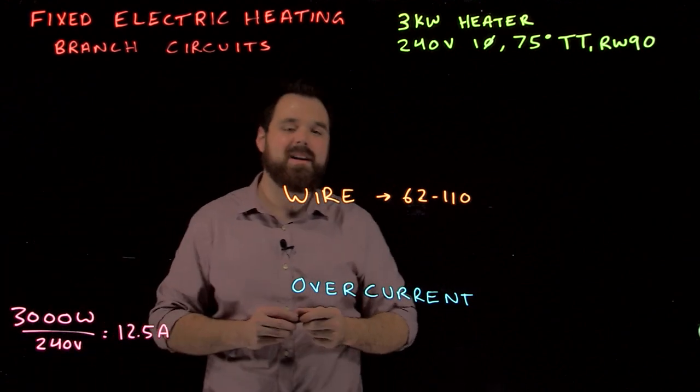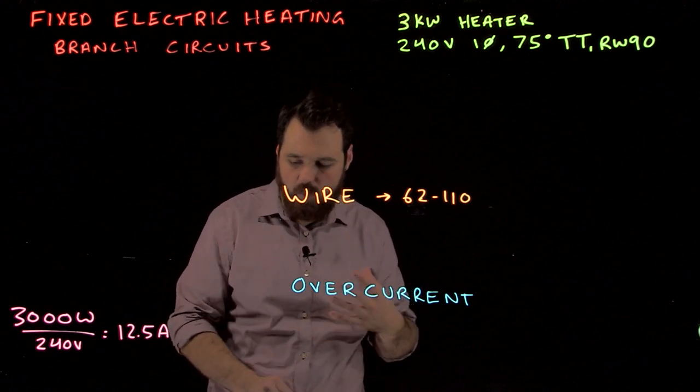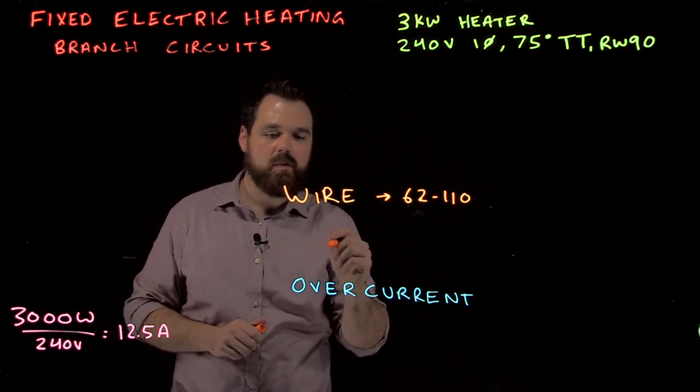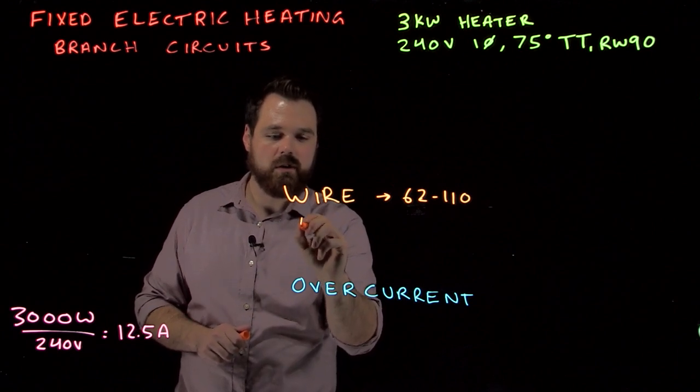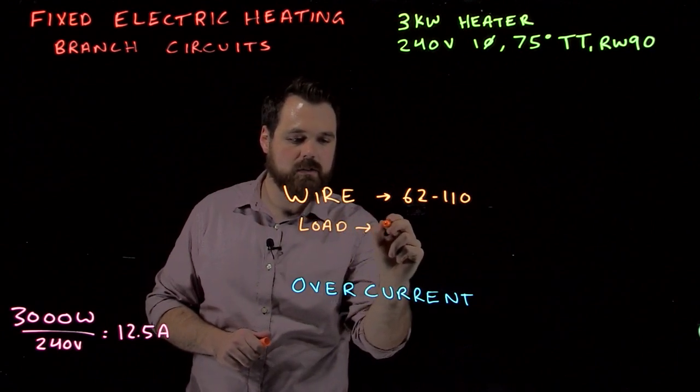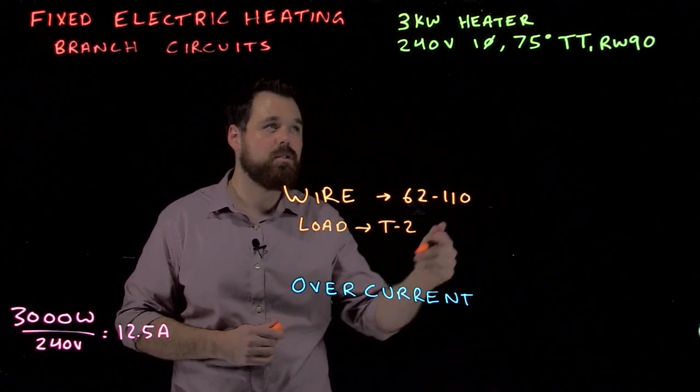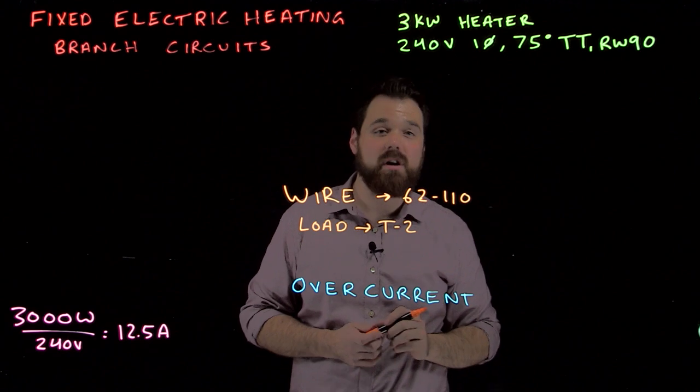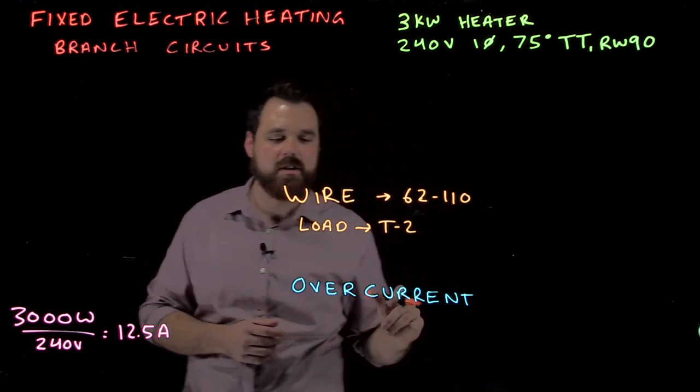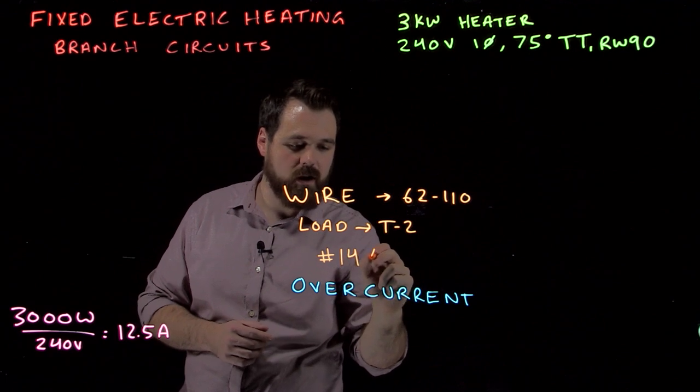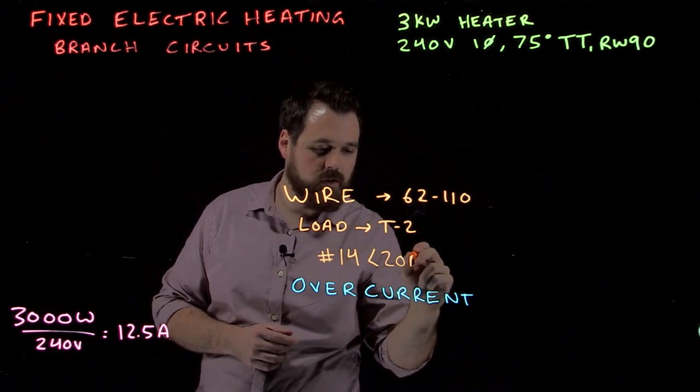That's the load that our wire needs to be able to carry. Well, in this case we take our 12.5 amps, we go with our load directly to table 2. In this case, table 2, using the 75 degree column due to our 75 degree termination temperature, we end up with a number 14 gauge wire which is good for 20 amps.